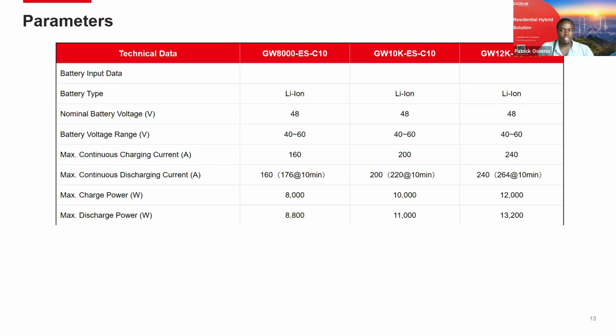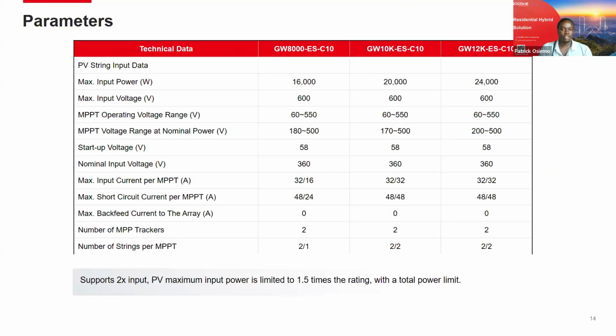Also mark that the charging and discharging of the battery depends on the battery itself, because ES Unique is also compatible with other third-party batteries. If the battery is capable of taking in that high power, then yes, the inverter will be able to charge and discharge the battery at these particular ratings. At the string inputs, you can see we are able to oversize the inverter to double the size. So on 8 kilowatt, you can do a 16 kilowatt PV installation. The same goes across the board, so the 12 will take in 24 kilowatt PV installation sizes.